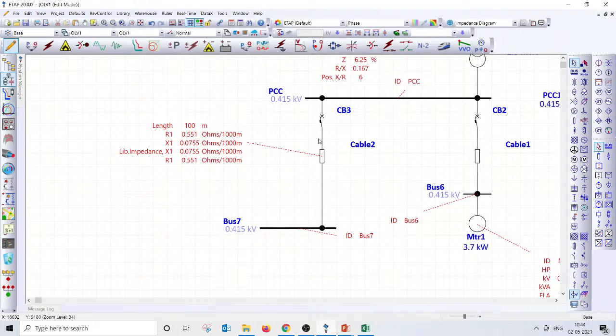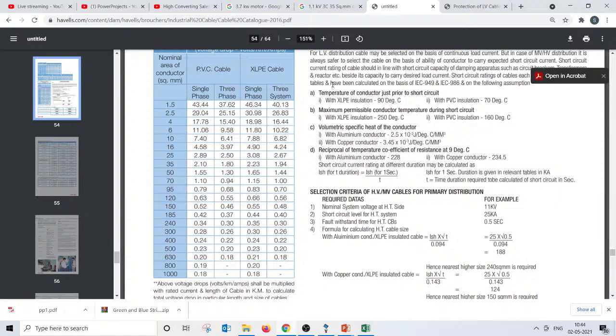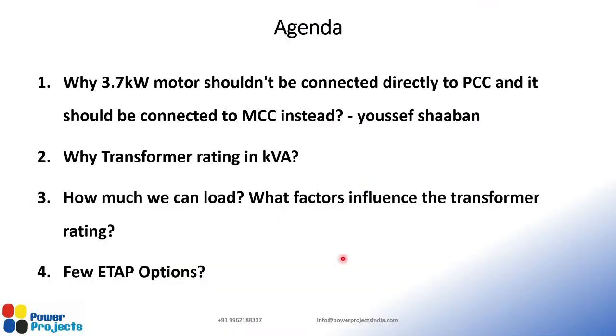I guess there are some points which you have taken out from our presentation today. Why should a 3.7 kilowatt motor not be connected directly to the PCC and should be connected to an MCC instead? The answer is, if you connect a 3.7 kilowatt motor directly at the PCC, the short circuit level is higher, though the current is only 7 amps, and to carry the full load current of 7 amps, a 2.5 square mm cable is more than sufficient.